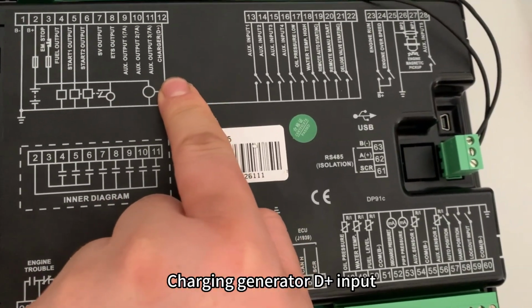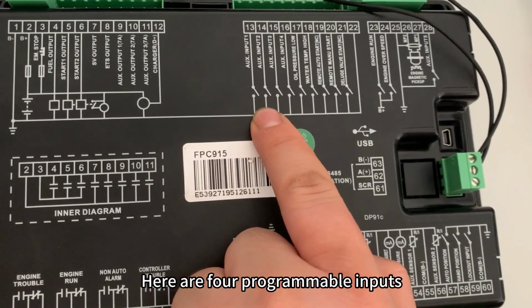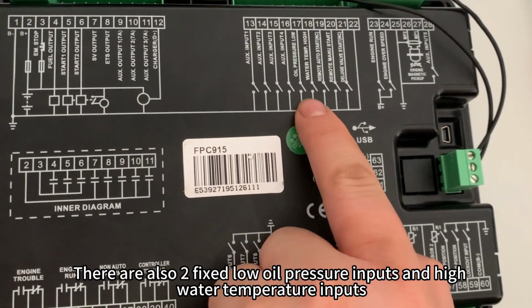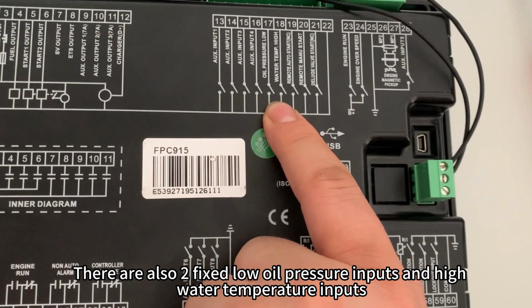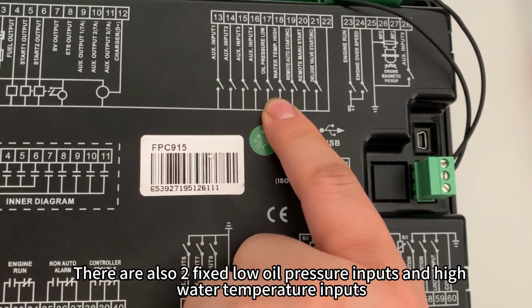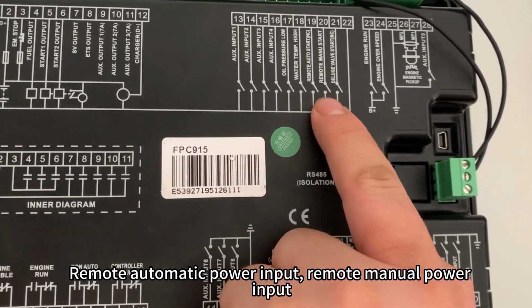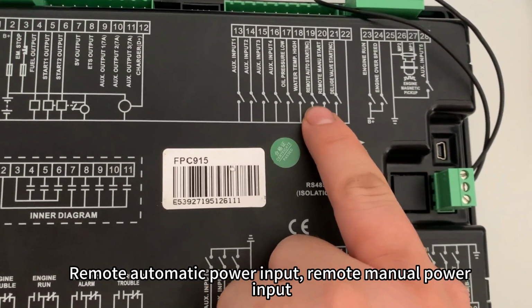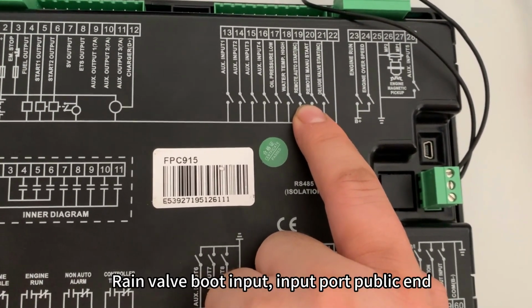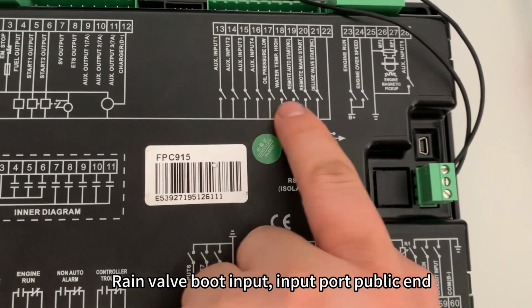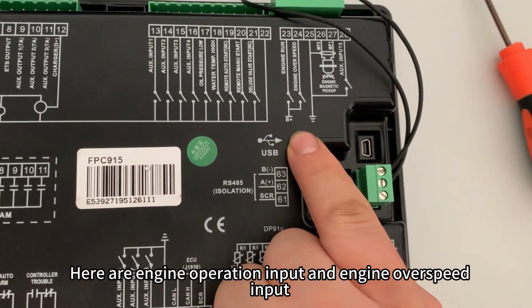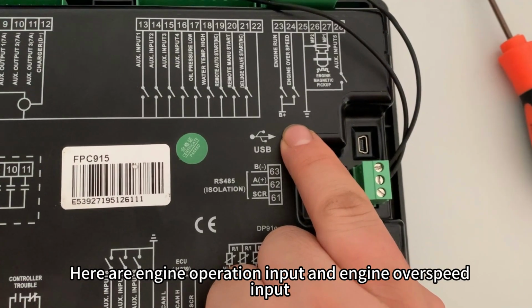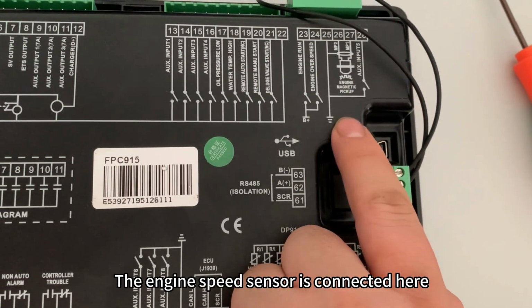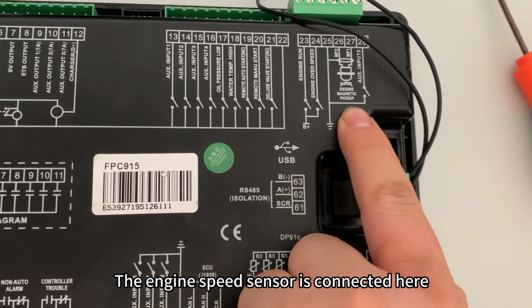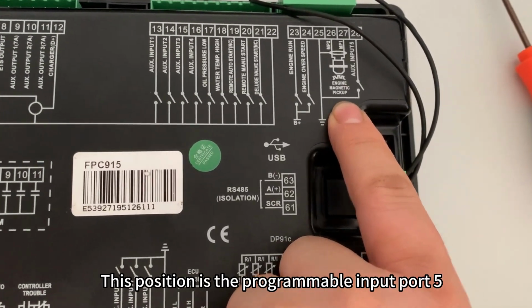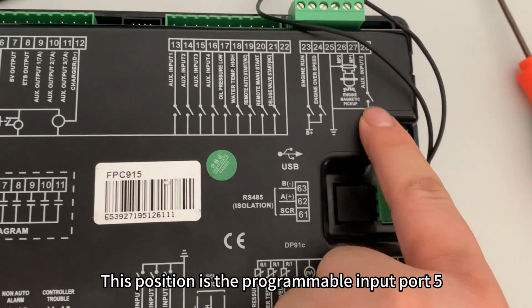Charging generator D+ input. Here are 4 programmable inputs. There are also 2 fixed inputs: low oil pressure and high water temperature. Remote automatic input. Remote manual input. Rain valve start input. Input port common end. Here are engine running input and engine overspeed input. The engine speed sensor is connected here. This position is programmable input port 5.